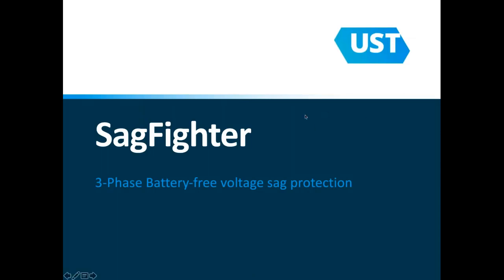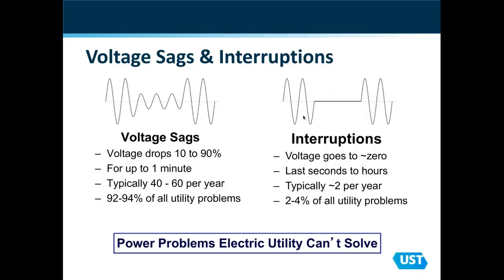So now we're going to talk about the Sag Fighter, which is a sag mitigation device. And again, as we talked about earlier, there are interruptions and there are sags. Our approach with this product is that a facility will experience far more sags on a per year basis than interruptions. Generally here in the US, power grid is pretty good. Not too many interruptions occur. But there are sags. Sags occur because of weather-related events, or oftentimes utility changes and switching on the grid that may cause a quick sag.